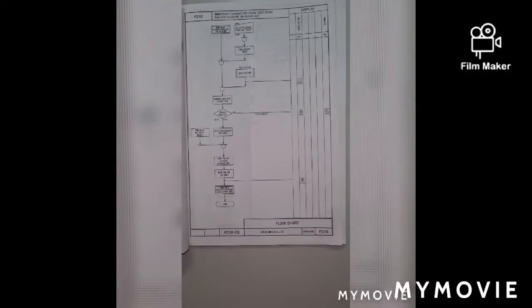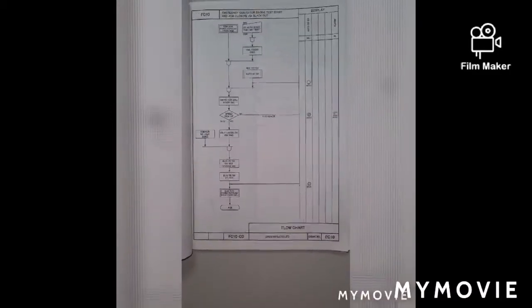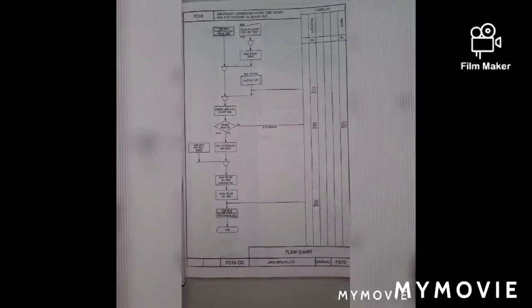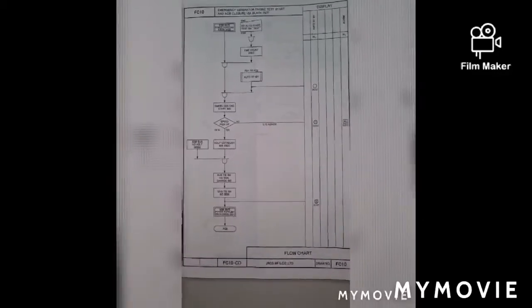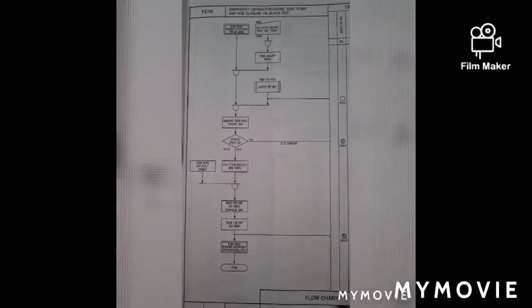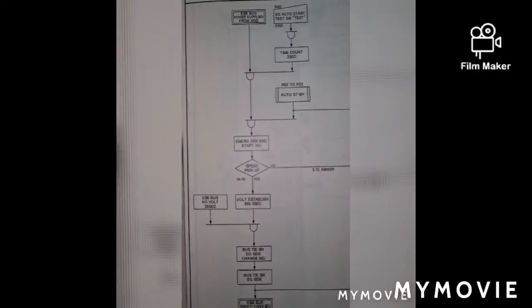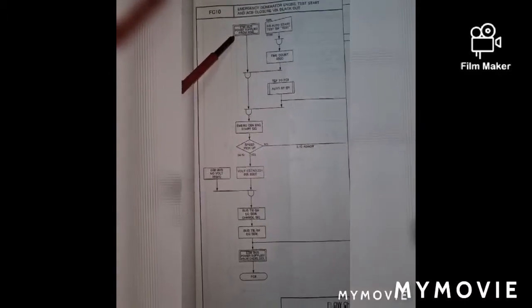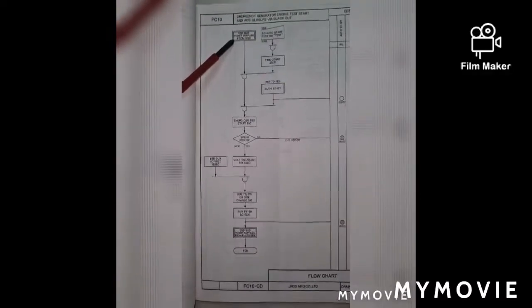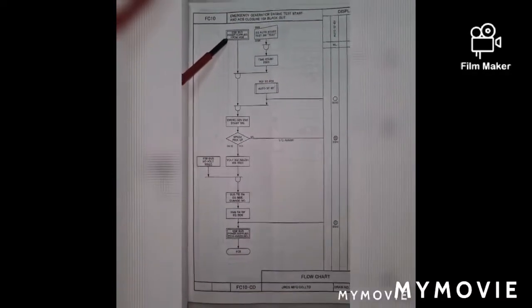Emergency generator engine test start and air circuit breaker closure by a blackout. This engine test start and air circuit breaker closure by a blackout test is made using a changeover switch. This is normally done once every month. In order for you to do this, you must keep the emergency generator control panel mode selector switch in automatic position.